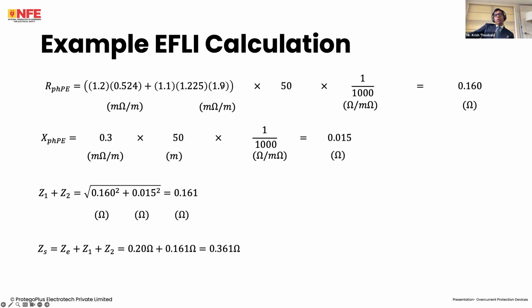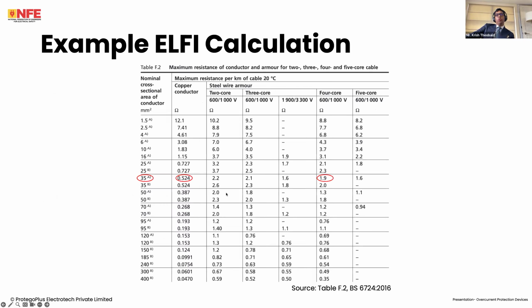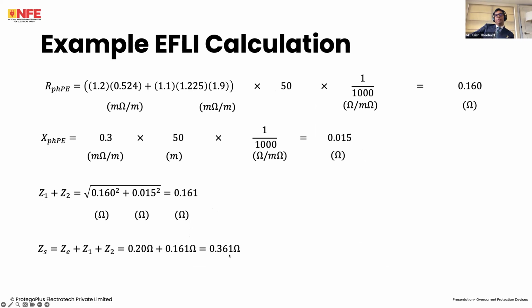1.1 times 1.9, which is the value for the armor, has to also be multiplied by 1.225 to consider that the armor is now at 70 degrees. Multiply by 50 meters, go from milliohms to ohms, you get 0.160 ohms. The resistive component is now taken care of. The reactive component, 0.3 milliohms per meter. Remember, no parallel conductor. Multiply by 50 meters, 0.015 ohms. Z1 plus Z2 is equal to the square root of 0.160 squared plus 0.015 squared, 0.161 ohms. External earth fault loop impedance is 0.20. So 0.20 plus 0.161 is 0.361 ohms. Simple.